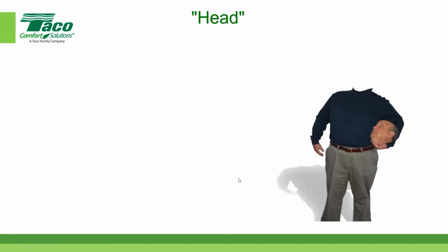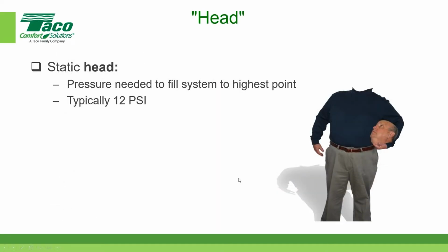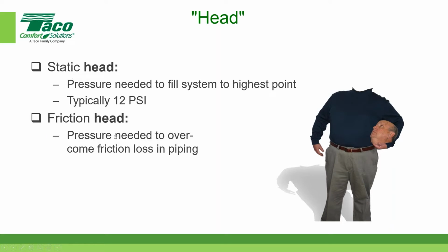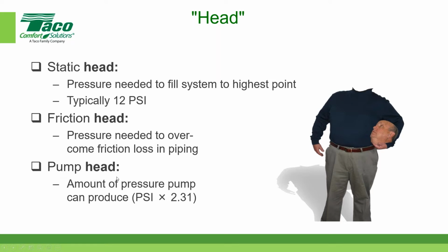But anyway, let's talk about just the term head again. You'll see terminology. People say static head, and they'll use the term friction head, and they'll use the term pump head, and all those are applicable within our industry, and you'll hear them used. I just want you to understand what they mean by it. Just don't say head pressure. So static head is the pressure, friction head is the pressure, and pump head is the amount of pressure, etc.